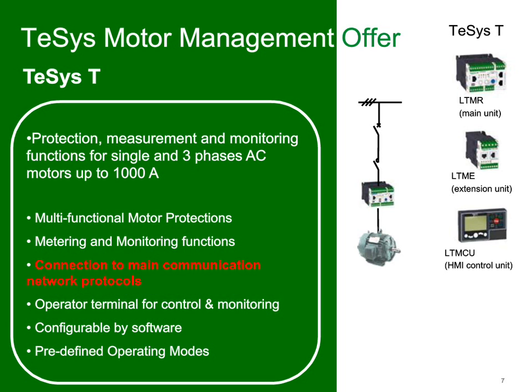The LTME is a device that mounts adjacent to the LTMR, and that has 3 voltage taps on it so that we can do current with the LTMR and then voltage with the LTME. And so with current and voltage, we can do power in watts. So we're telling you that we not only can measure the current here, but we have an energy meter built right into the motor overload.